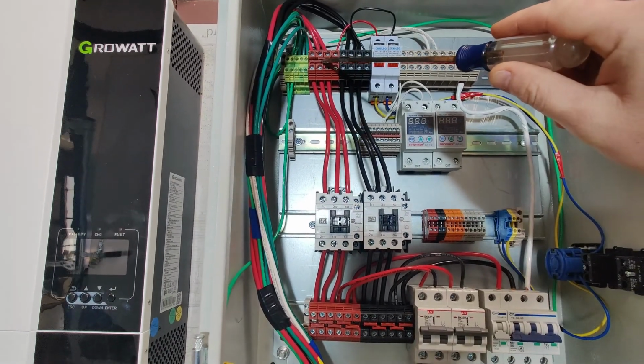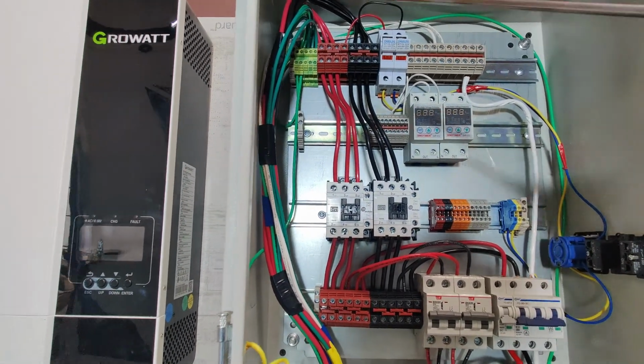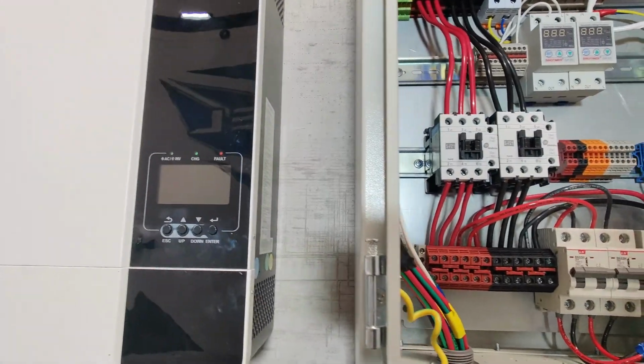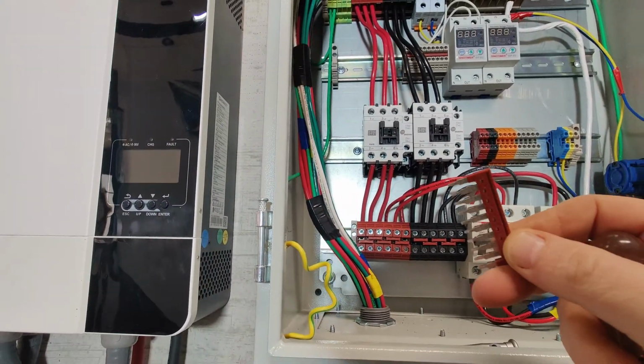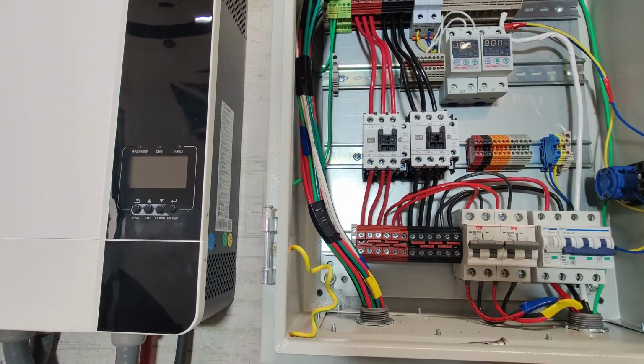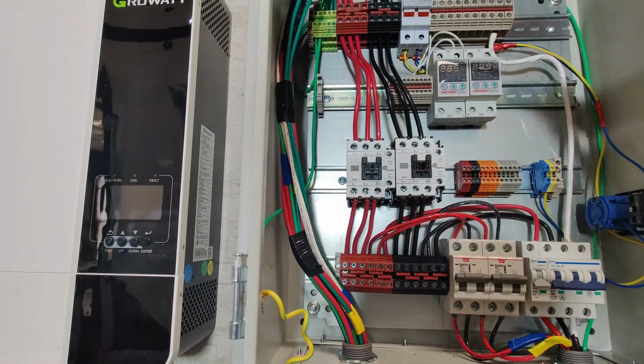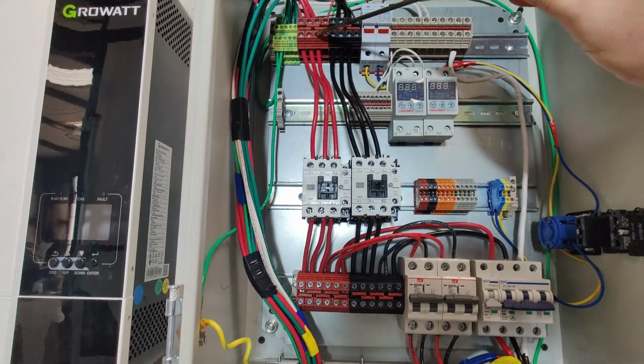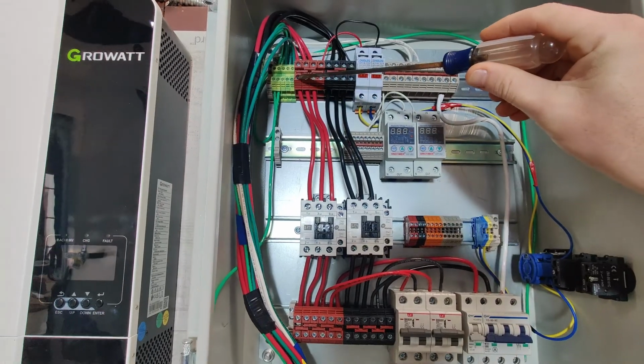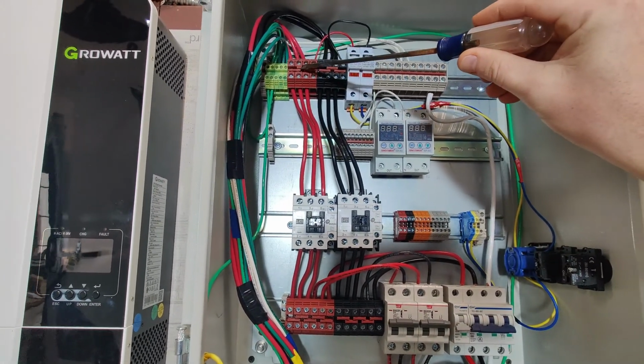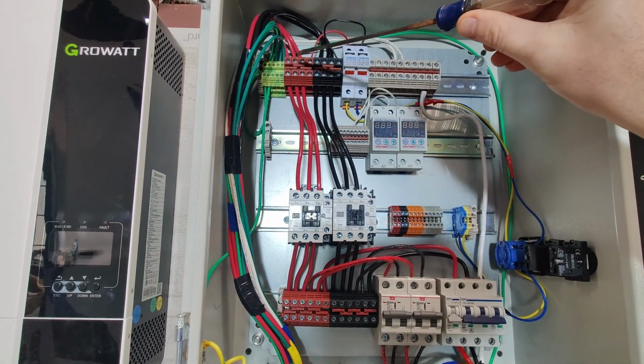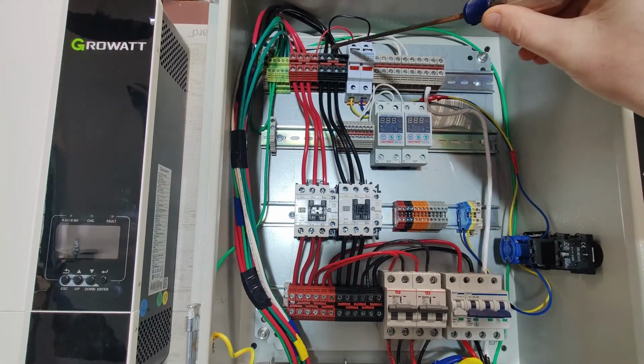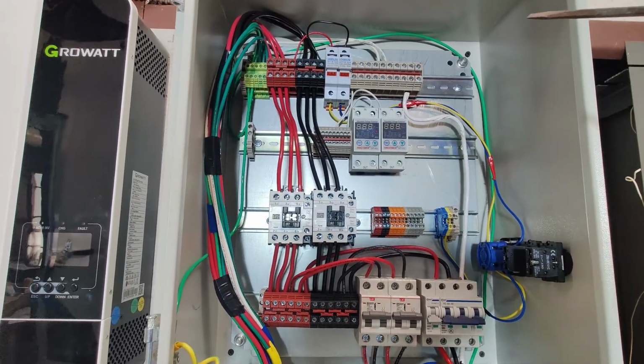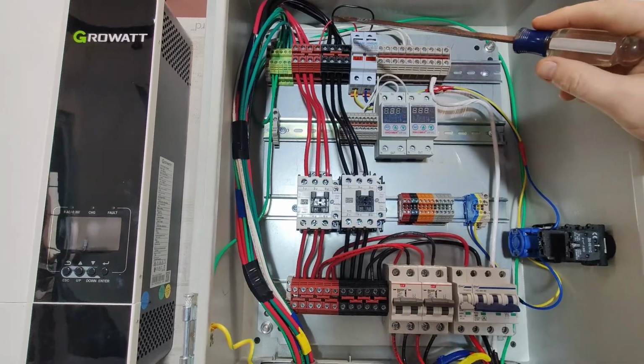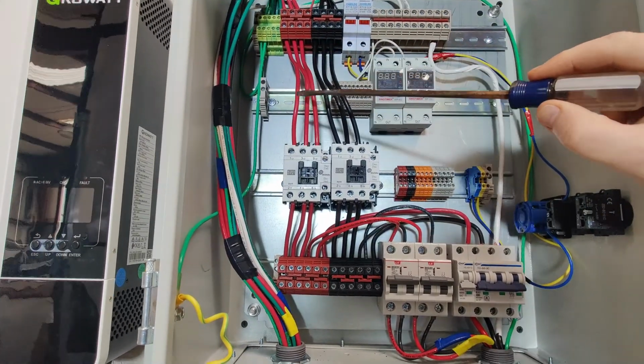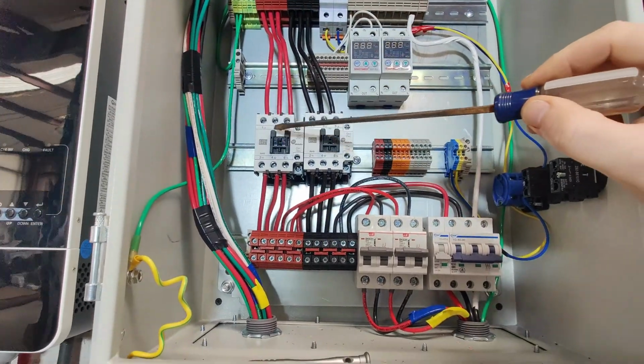So we have all these little connectors, and what these connectors do is allow you to join multiples of these Dinkle connectors together. And when we join those together, we're essentially paralleling the inverters right here, right when they come into the box. This is similar to what happens in a circuit breaker. So they come out of here in 3 different wires, and they come down to the contactor.